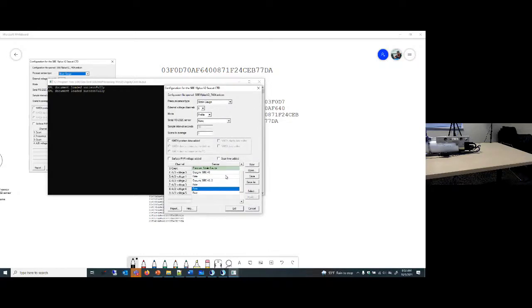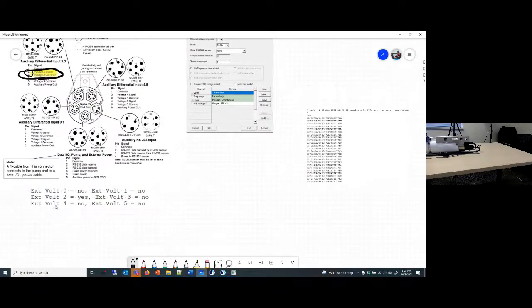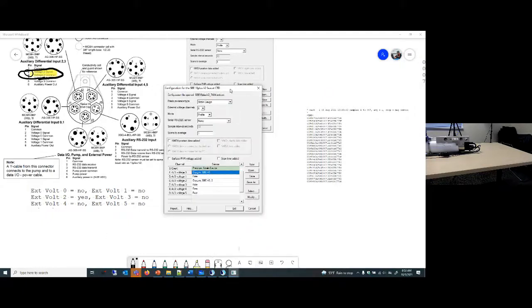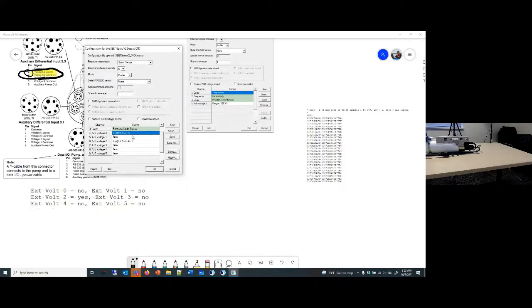But in reality, that's incorrect. If you have 6 external voltage channels enabled on your XMLCon file here, it's going to think that you have volts 0, 1, 2, 3, 4, and 5 enabled. If you don't have those enabled, this XMLCon file is not going to match up with your CTD's configuration, and you won't be able to process your data.